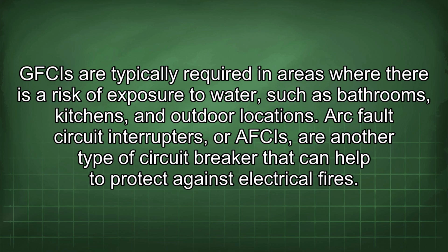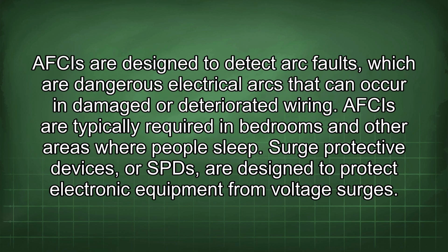Arc fault circuit interrupters, or AFCIs, are another type of circuit breaker that can help to protect against electrical fires. AFCIs are designed to detect arc faults, which are dangerous electrical arcs that can occur in damaged or deteriorated wiring. AFCIs are typically required in bedrooms and other areas where people sleep.